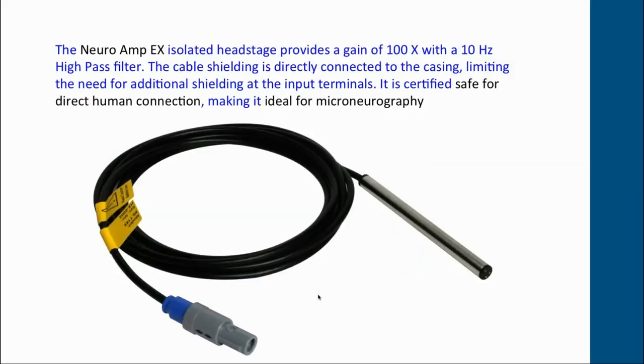The head stage — a stainless steel cylinder and cable — provides preamplification with a gain of 100 and a high-pass filter of 10 Hz. The cable shielding is directly connected to the casing, which limits the need for additional shielding of the input terminals. The input terminals are very high impedance and, importantly, they have input protection circuitry.